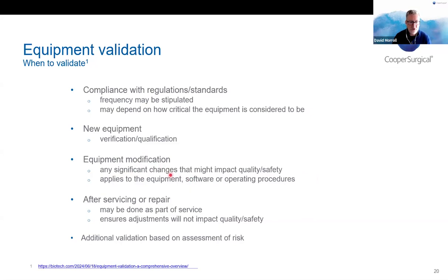And just be aware, it's not just the equipment, it might be the software, but it also might be the way that piece of equipment is used. So again, it's linking the equipment validation to the process validation, because they are inherently connected. The other thing to say is that it's good practice to revalidate after servicing or repair. So we tend to focus on servicing as a way of making sure our equipment is working well. That servicing needs to include some degree of revalidation, recalibration. So it may be done as part of the service. So that's part of the discussion to have with your service engineers, your service company.